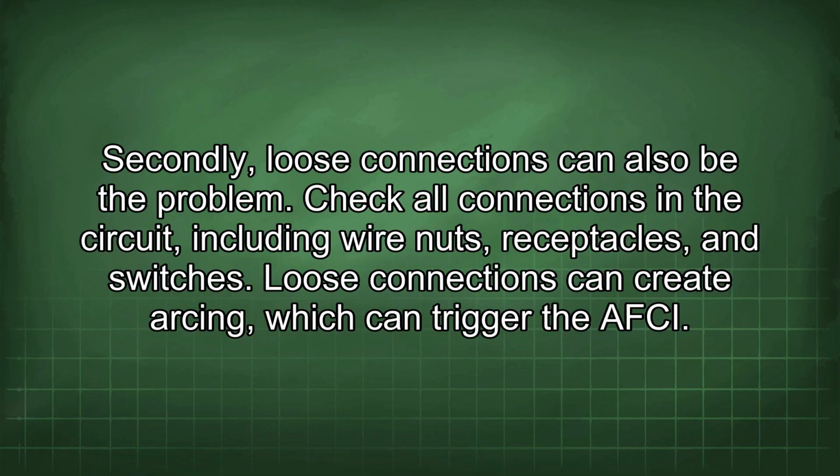Secondly, loose connections can also be the problem. Check all connections in the circuit, including wire nuts, receptacles, and switches. Loose connections can create arcing, which can trigger the AFCI.